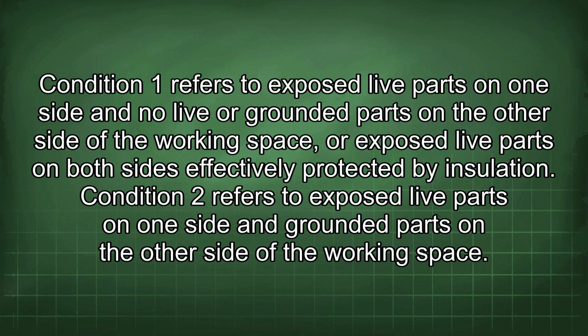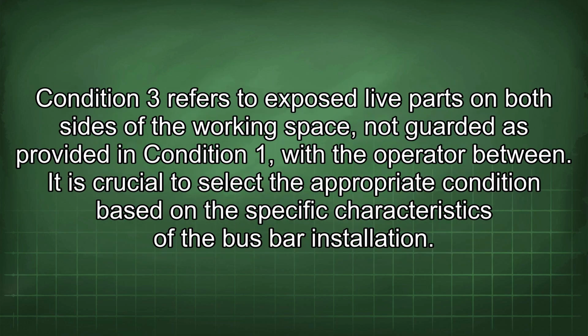Condition 2 refers to exposed live parts on one side and grounded parts on the other side of the working space. Condition 3 refers to exposed live parts on both sides of the working space, not guarded as provided in Condition 1, with the operator between. It is crucial to select the appropriate condition based on the specific characteristics of the bus bar installation.